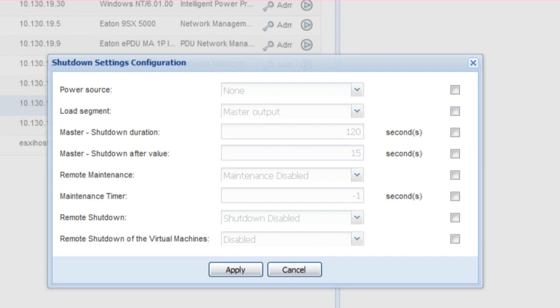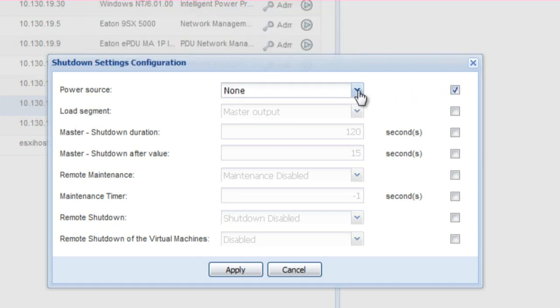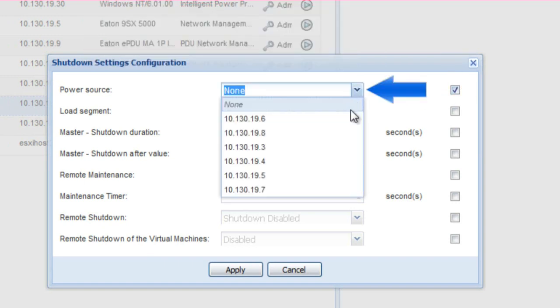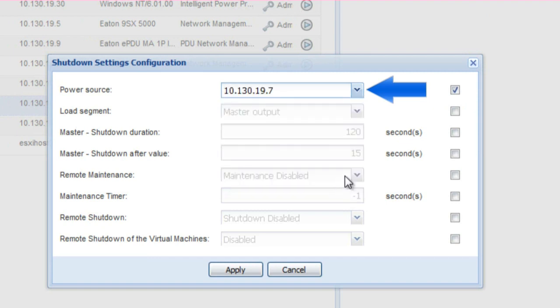The maintenance configuration will need the following parameters set. Power Source: select the IP address of the UPS which powers your host. Load Segment: designate the output receptacle which the host node is connected to on the UPS. Typically, this will be the master segment.